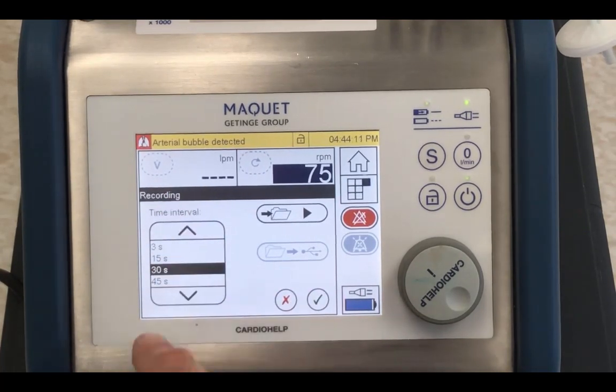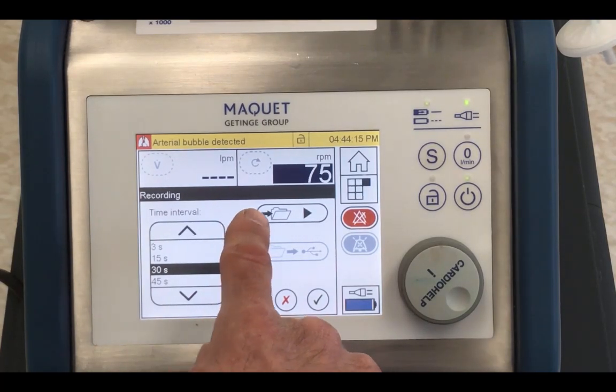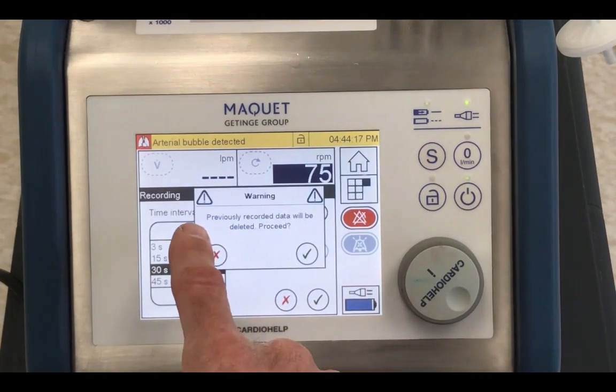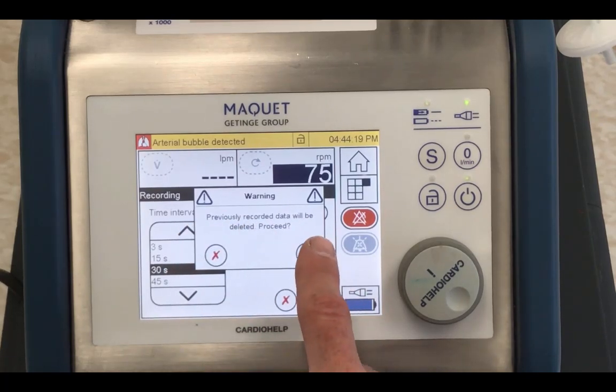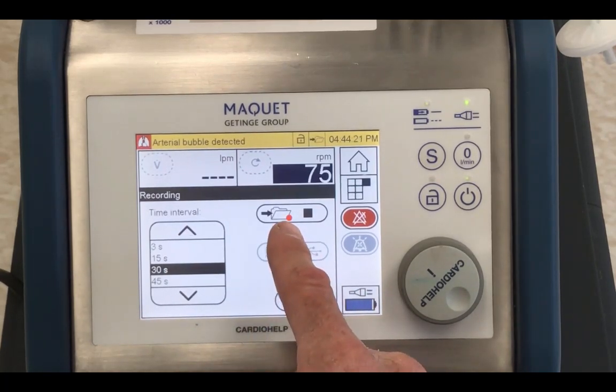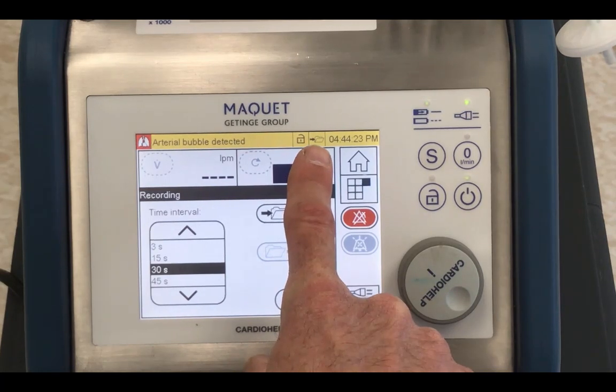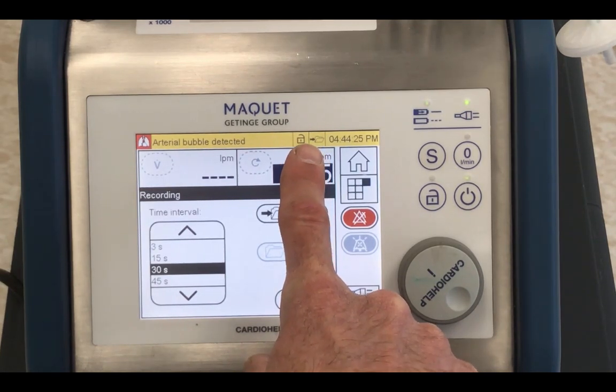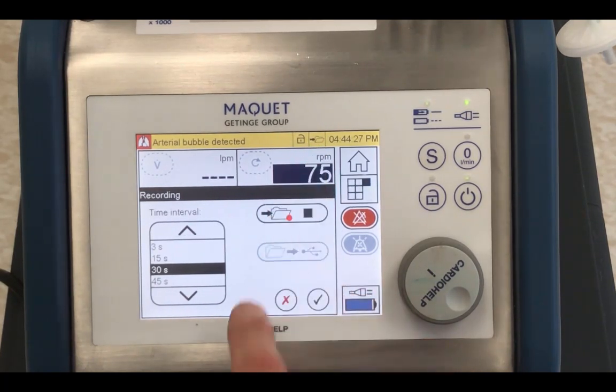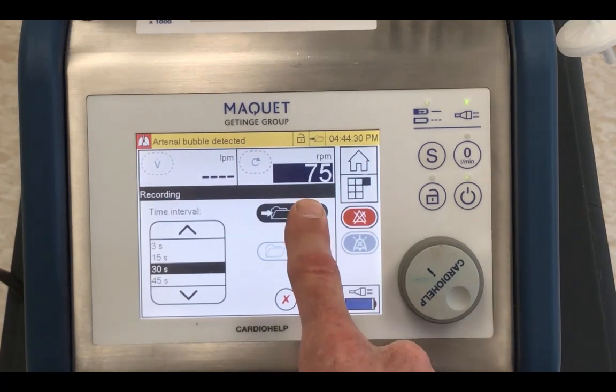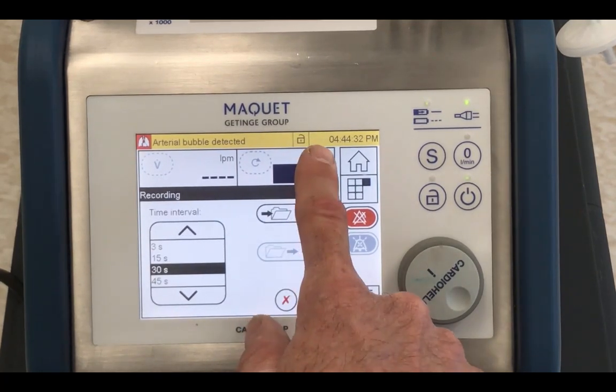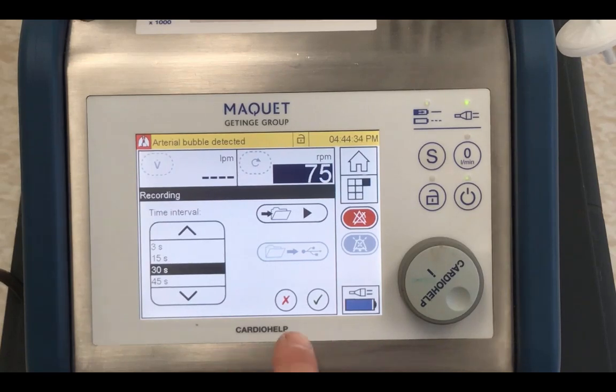And so you pick your interval, and then you have to turn it on. You have to tell it, put the data in the folder. Previously recorded data will be deleted. That's okay. You hit that. Now data recording is on. And you notice up here in that little real estate space I was telling you about earlier, there's now an arrow pointing at a folder to tell you that you are recording data. And we can stop recording data. And it goes away from that menu up there.